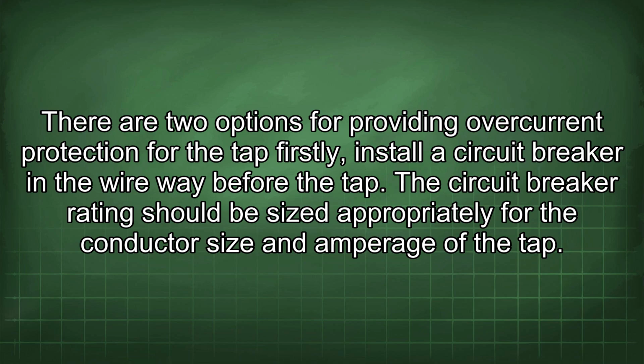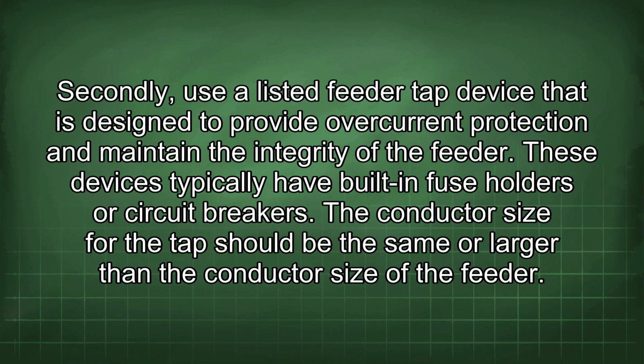Firstly, install a circuit breaker in the wireway before the tap. The circuit breaker rating should be sized appropriately for the conductor size and amperage of the tap. Secondly, use a listed feeder tap device that is designed to provide overcurrent protection and maintain the integrity of the feeder. These devices typically have built-in fuse holders or circuit breakers.